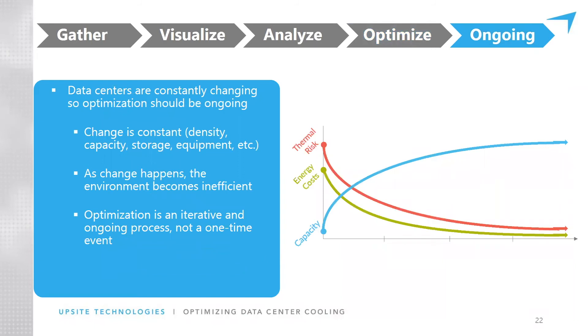The key to this is that it's ongoing. It's possible for an individual with experience in this field to walk into a data center, take measurements, provide recommendations, adjust set points, rearrange supply tiles, and get the room optimized — but then it drifts, and over time all of those benefits fade away because of the changes that occur. This graph shows that when you deploy these tools and start making changes, you get huge benefits very quickly, which really helps with the simple payback of deploying these tools.